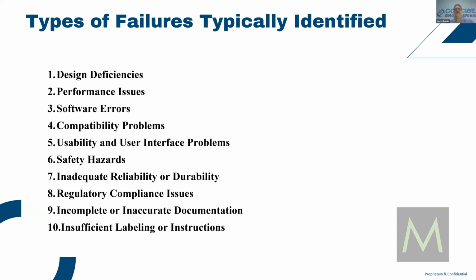All right, when you get into failures, I can't say this is a complete list, but this is a pretty substantial list. You're going to find stuff where you didn't design it correctly. You're going to find something from a performance perspective where you didn't exactly meet a torque or a requirement. Ideally, you're doing all this stuff early and you're in the stage of design so that you're not finding out last minute, as Mark had mentioned before. You're going to have software errors and anomalies within your product. You may have some compatibility problems, and these could be related to different types of materials. It could be like we were talking about, tolerance stack up issues.